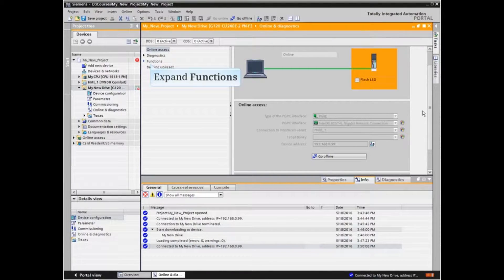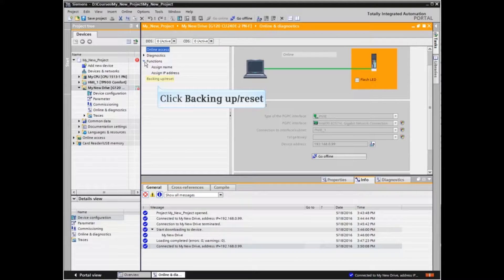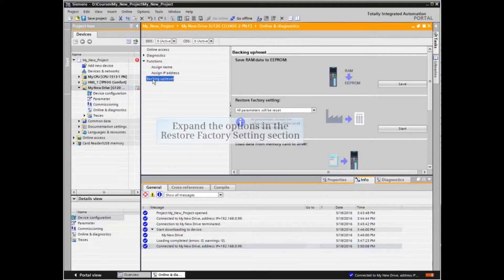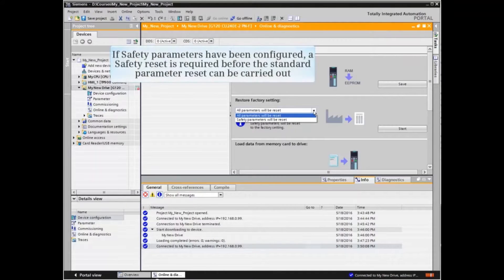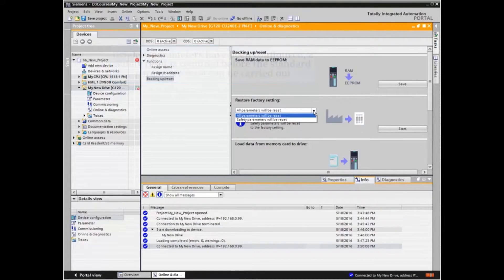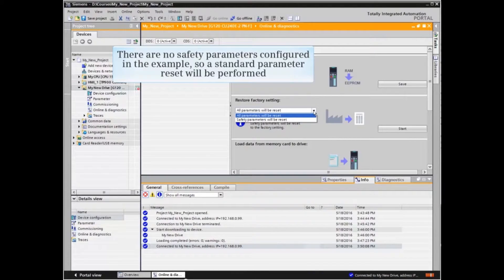From the menu tree in the Online and Diagnostics screen, expand the Functions listing and click the Backing Up and Reset listing. Expand the options in the Restore Factory Setting section. Note that there are options to reset the standard parameter set or the safety parameter set. If safety parameters have been configured, a safety reset is required before the standard parameter reset can be carried out. There are no safety parameters configured in this example, so a standard parameter reset will be performed.